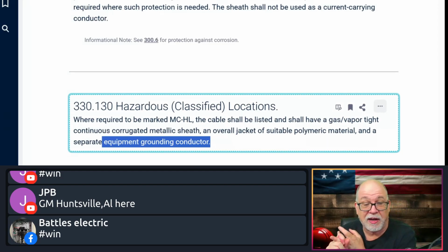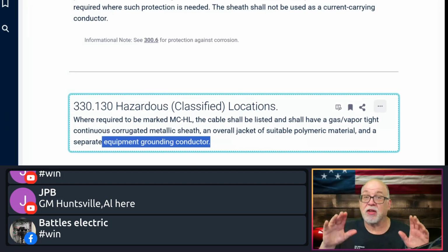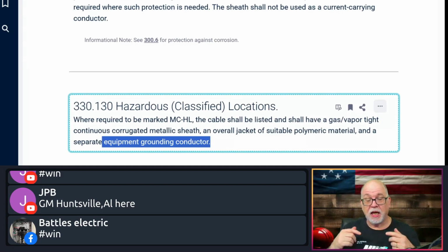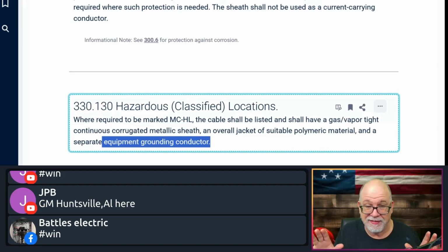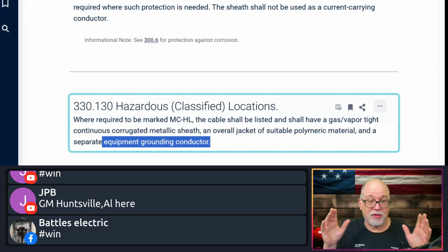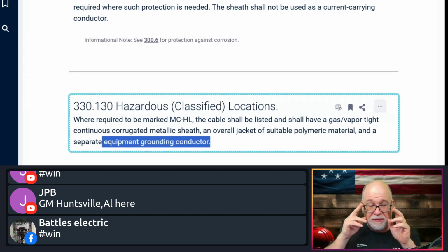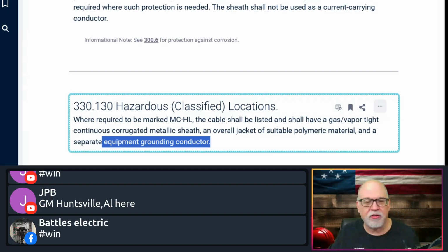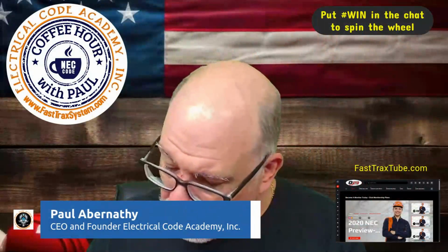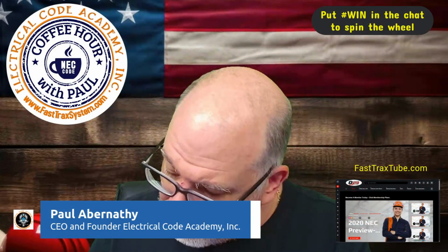Now, for all of those haters out there that say, wait a minute, I can't use, and again, Code Panel 17 members, listen up. If you say that I can't use PVC jacketed MC in a swimming pool application, then I'm going to tell you, wait a minute. PVC material, polymeric material, has a very high resistance to corrosion. Get over it. It's okay. We don't have any historical effects that cause problems, and we provided that data to the code panel. I believe the way the words are now, we get around that because I believe it is rated for such. But again, there are still some people out there that don't understand. Okay. Let me write that down so I don't forget there, Ryan.